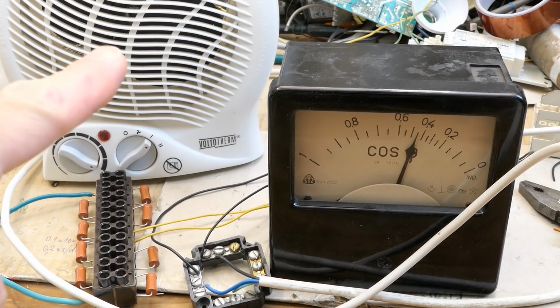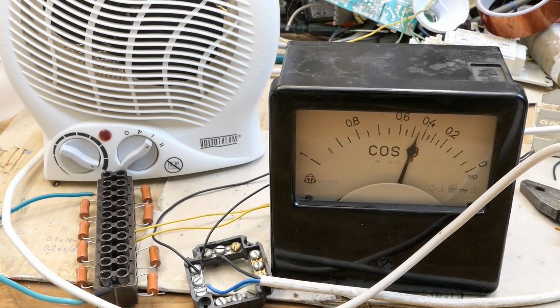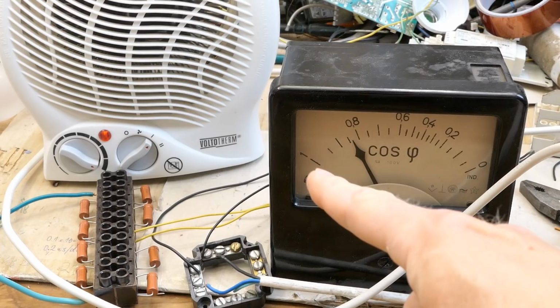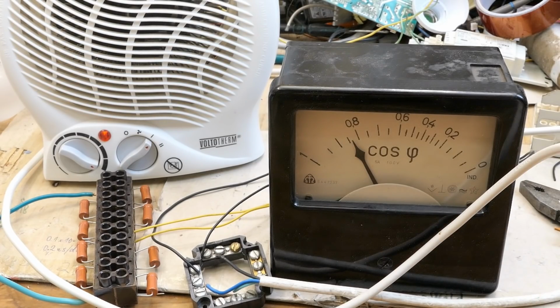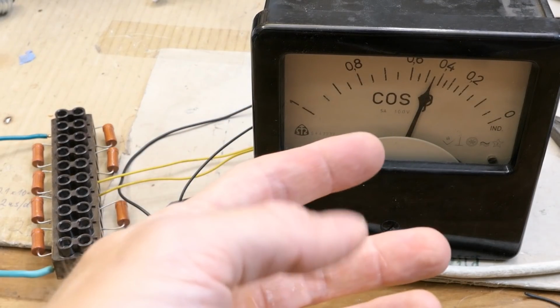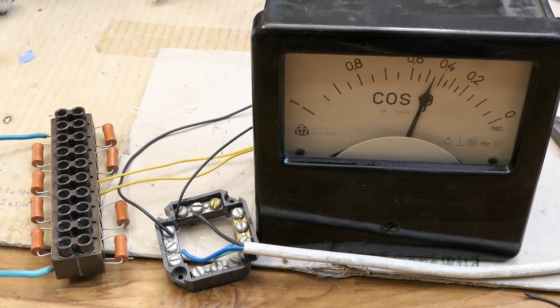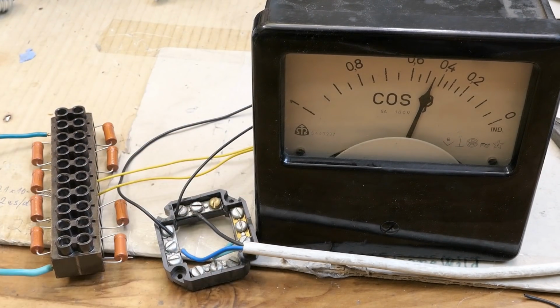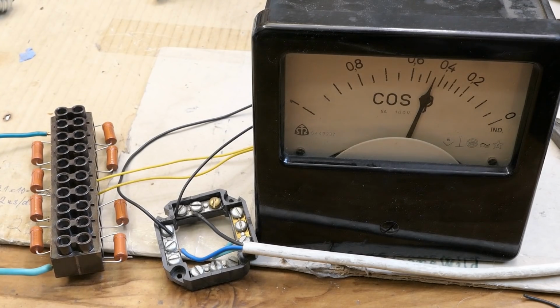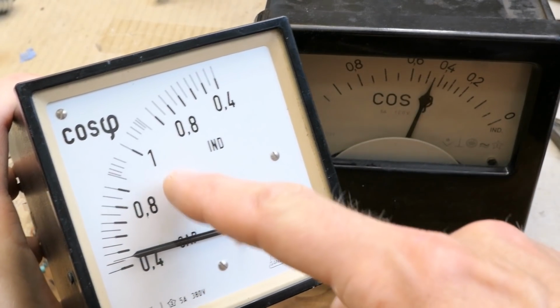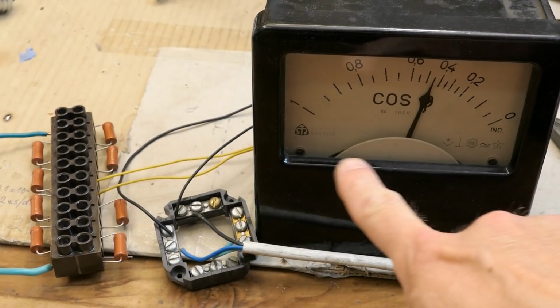A 1 kilowatt heater, probably drawing a bit over 4 amps. It definitely goes to resistive, to 1, but still not enough. And of course the motor is negligible compared to the heater in it. This one is going the right direction, but not all the way. But making it operate is quite tricky, not knowing the original way it was meant to be wired. Maybe the wiring is different than this one, because this one is symmetrical with one in the middle and this one not. Let's quickly try this one.